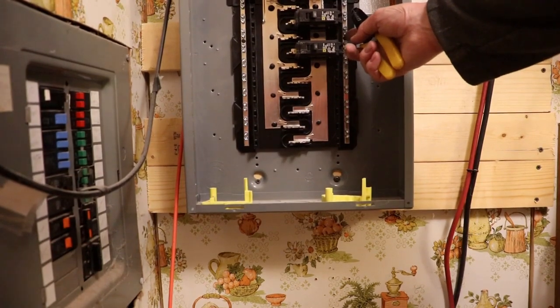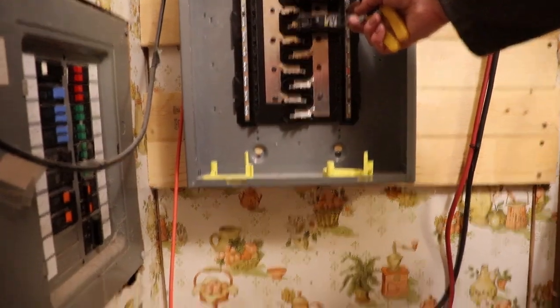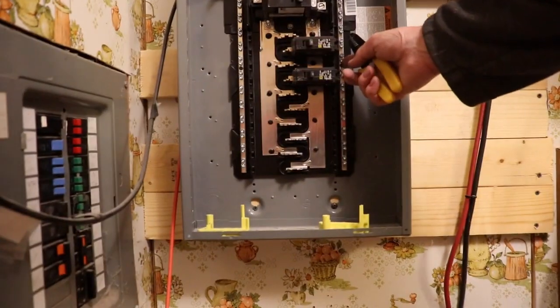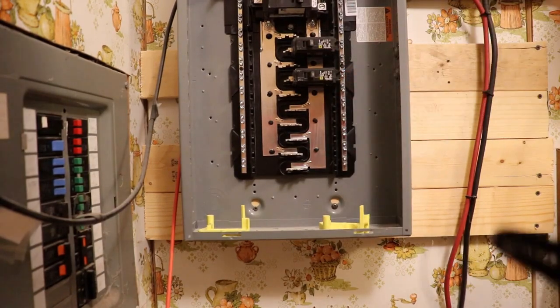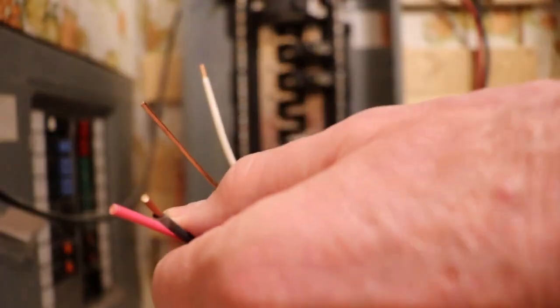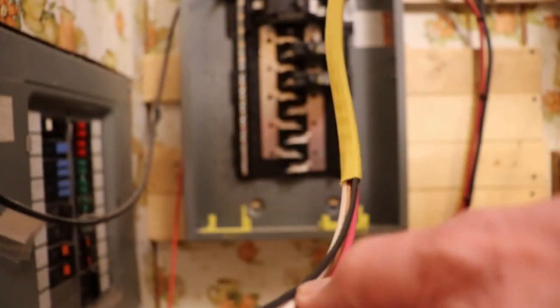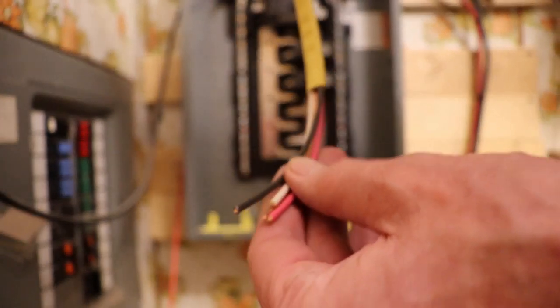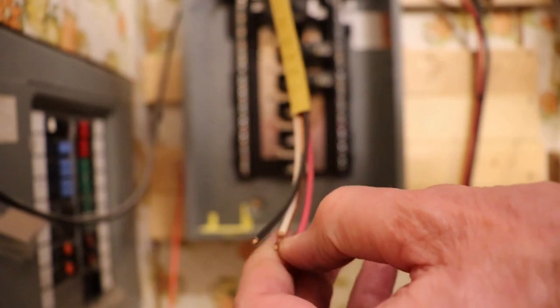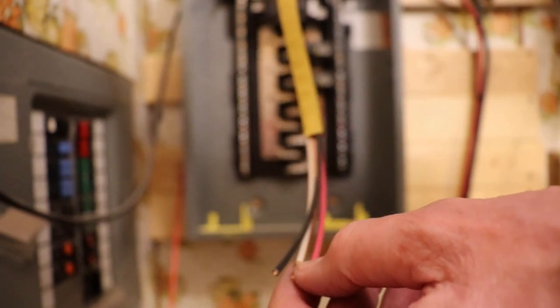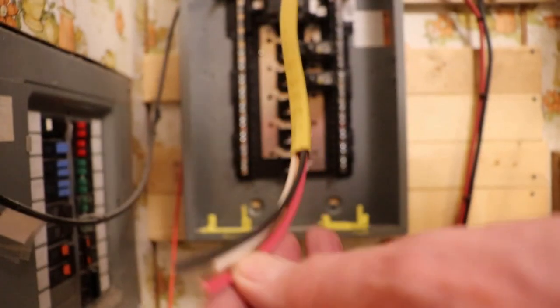The first circuit is all I'm wiring up tonight. I'm not doing the second one—even though this has two hot wire connections, I'm only using one, the black and white. The black is hot, the white is neutral. The red would be your second hot wire, and if you go with a third hot wire, it would be blue—so black, red, blue. And of course our ground wire is this right here.